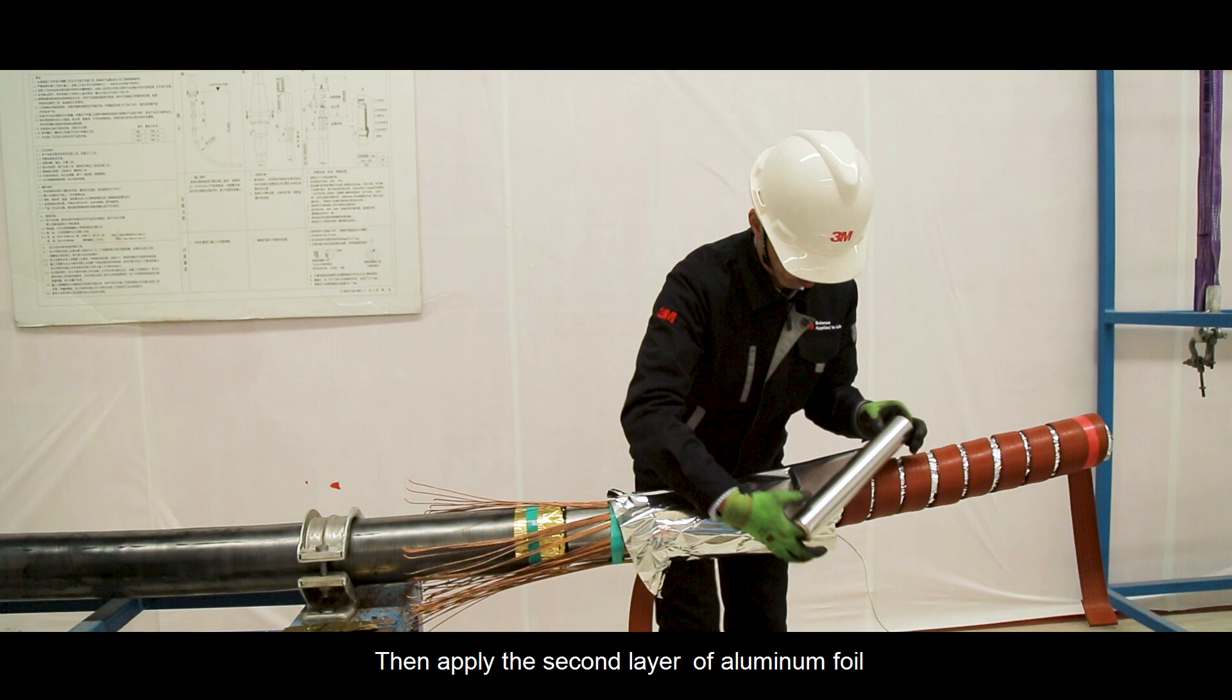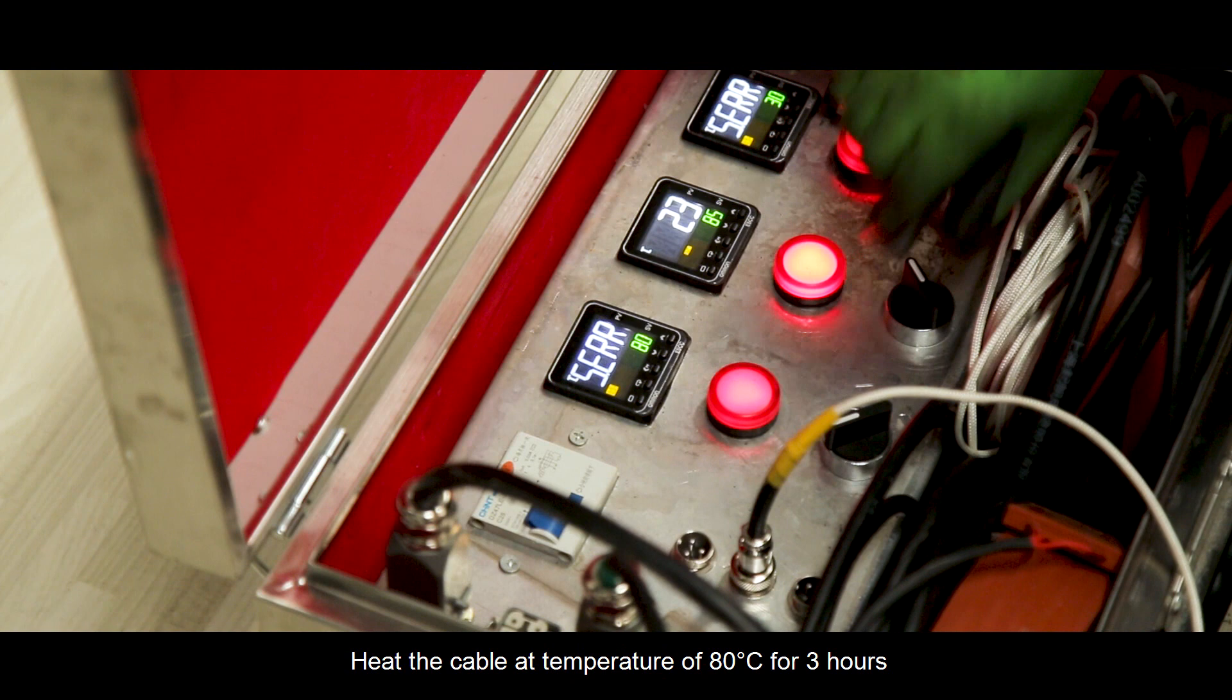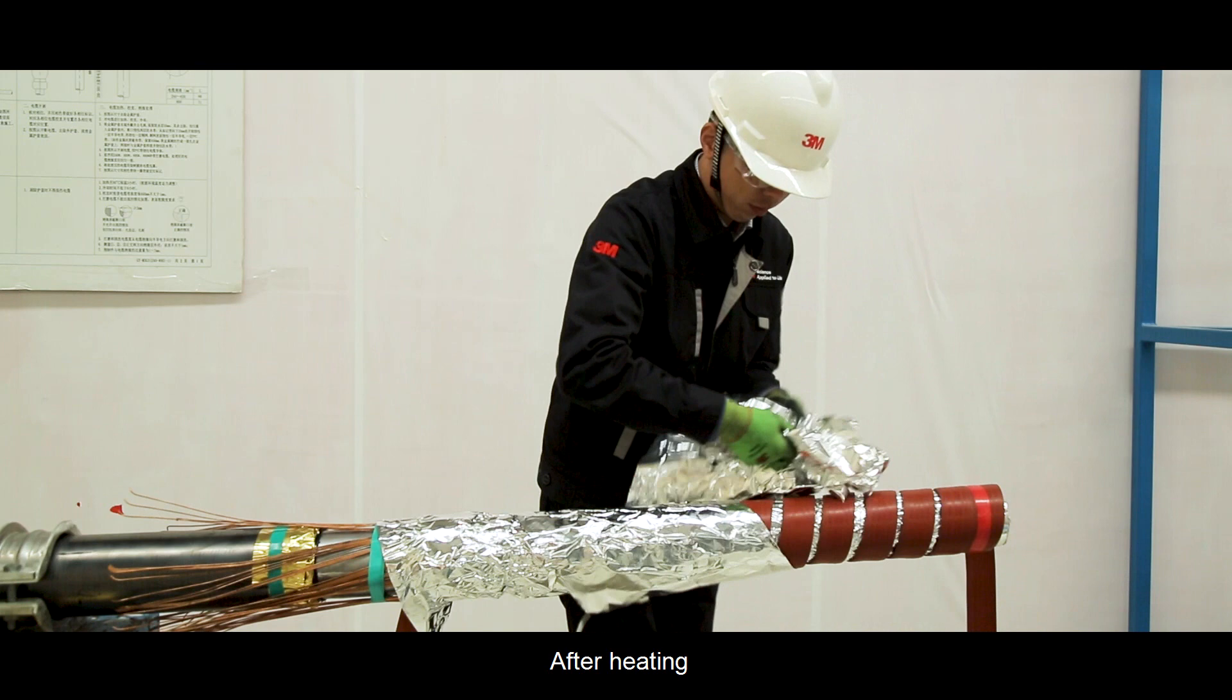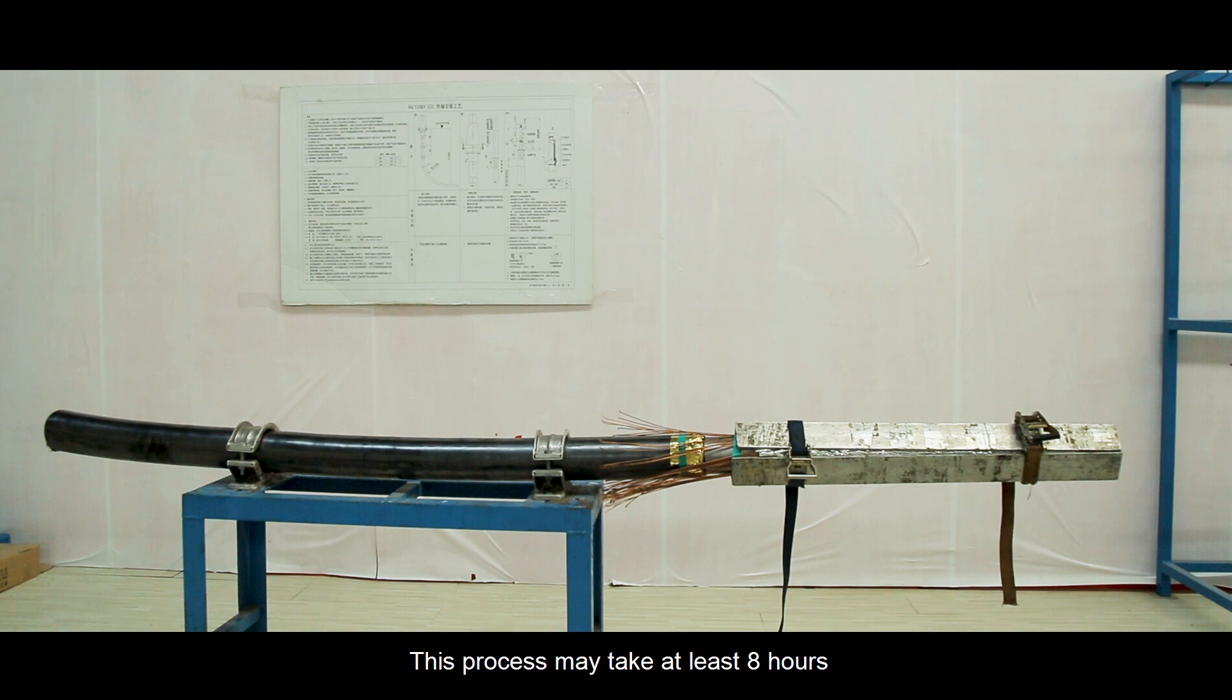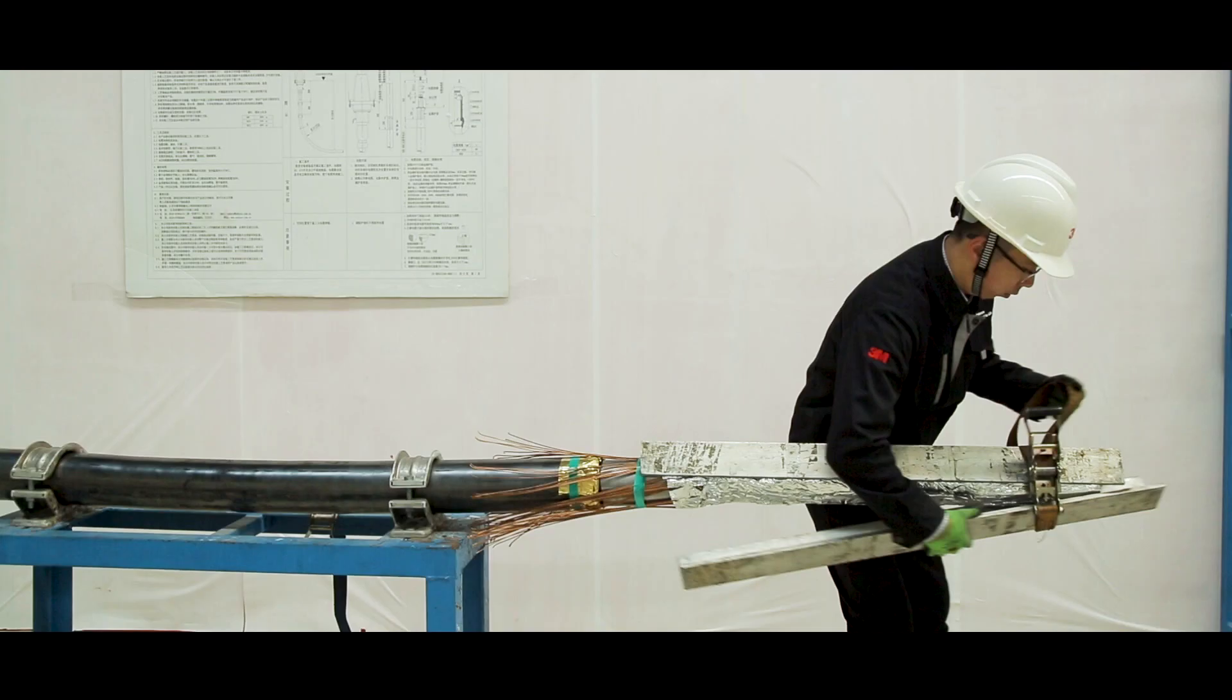Then apply the second layer of aluminum foil covering the heating tape. Heat the cable at temperature of 80 degrees Celsius for 3 hours. After heating, use angular aluminum plate to keep the cable straight and let it cool down to room temperature naturally. This process may take at least 8 hours.